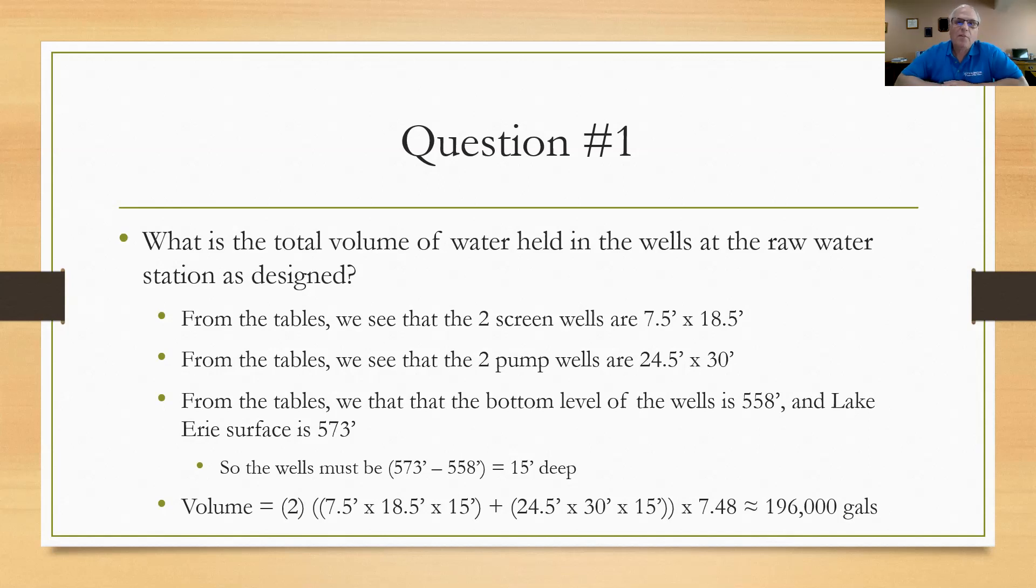So when we do the problem, we've got the volume of two clear wells so I put a two there, and I'm adding together the calculation of both of the wells. The first one was seven and a half by 18 and a half by 15 and the pump wells were 24 and a half by 30 by 15. Going to multiply those by two and convert them to gallons by multiplying by 7.48 and I get approximately 196,000 gallons. Hope you did well on that. And as I always remind you, if you want to work through these problems go ahead and pause the video at each time I offer you a question and you can try to work them out on your own.